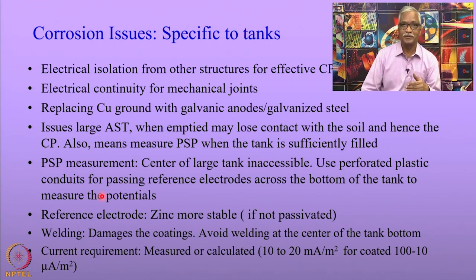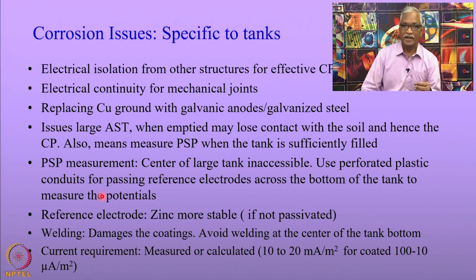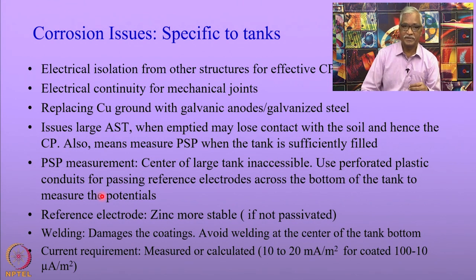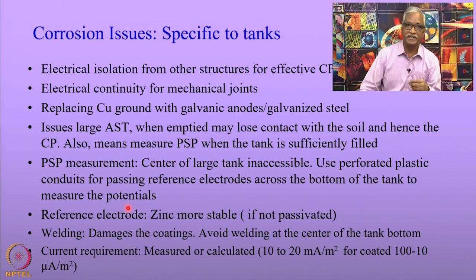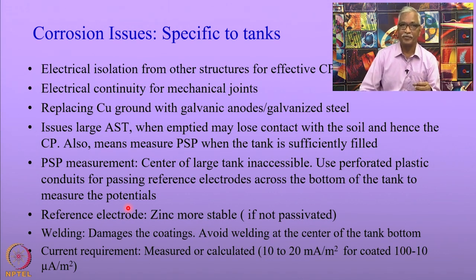There is a need to change these reference electrodes over time, which is not possible in the case of tank bottoms. So zinc electrodes can be used because they are buried in the soil — the only condition is that zinc should not be passivated. Zinc sometimes gets passivated if there are carbonates in the soil.